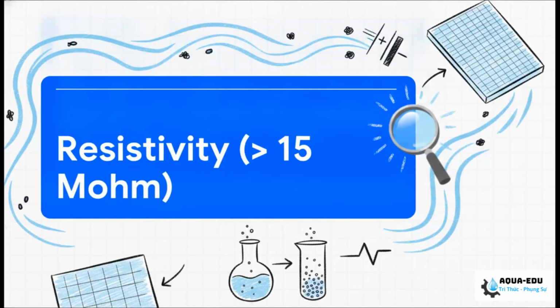And how do we actually measure that ultimate quality? Resistivity. In heavy-duty industries like semiconductor manufacturing, hitting a water resistivity greater than 15 megaohms is absolutely non-negotiable. It's make or break for production. That 15 megaohm mark tells us we have a near-total absence of conductive ionic impurities.